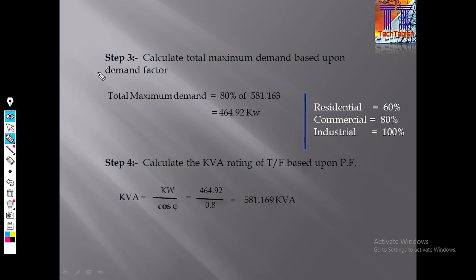This is the step 3. Okay, in step 3 calculate the total maximum demand based upon the demand factor. Now the demand factors come. So for demand factor, for residential is 60%, commercial is 80% and industrial is 100%. Here it is the commercial, so 80% of 581, that is 464.92 kilowatt. Okay, this comes in kilowatt.